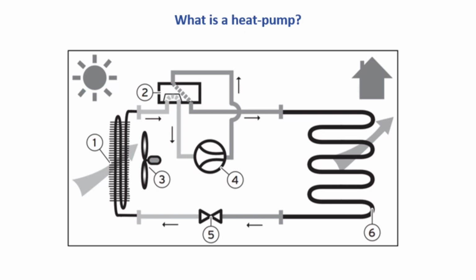So this reversing valve arrangement will allow the system to be reversed for defrost. So when the outdoor temperature is really low and if the humidity is high, you get ice building up on this surface. And so if we reverse this valve, we can use the compressor pump motor to drive the refrigerant into this radiator and heat it up. And the expansion valve is actually an electronic unit which closes off at this point, so that the flow can't keep going round in the other direction. It just only allows you to compress some of the refrigerant into this radiator, and then it heats up and defrosts. And once it's defrosted, it will start running in heat pump mode again.